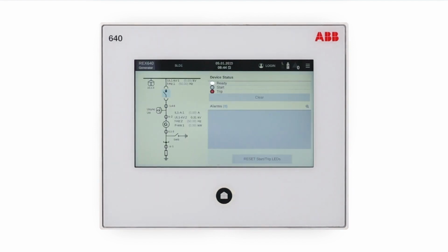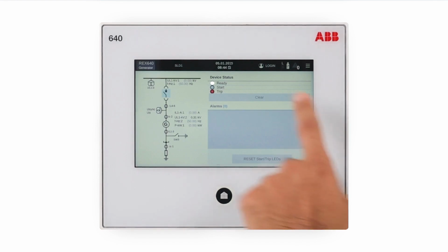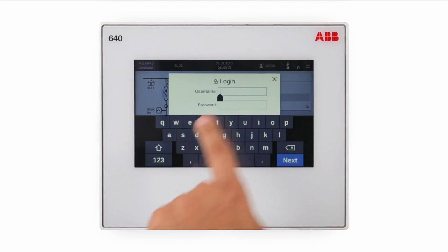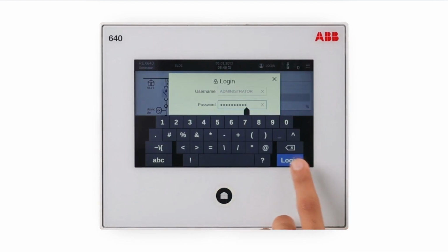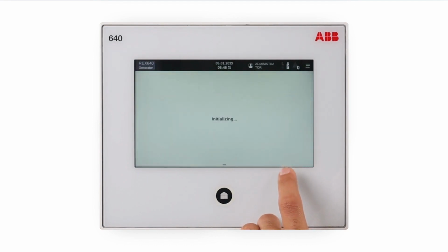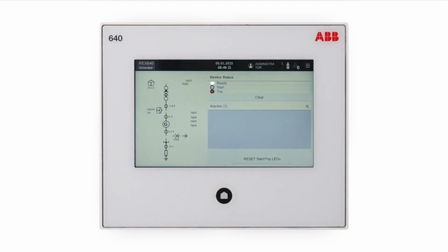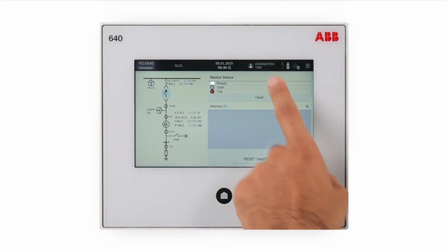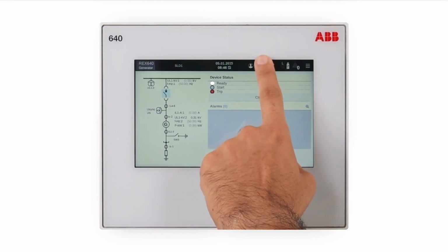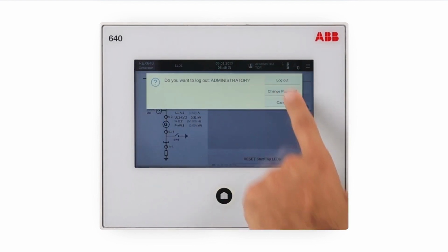Logging in. Once the HMI is connected to the relay, tap the login icon on the menu bar. Acknowledge the login banner notification if displayed. Provide the username and password in the dialog box. The user is logged in to the protection relay and the username is displayed on the menu bar of the HMI. If the login fails, then an error message will be shown on the login page. Logging out. Tap the username on the menu bar. Tap Log Out.